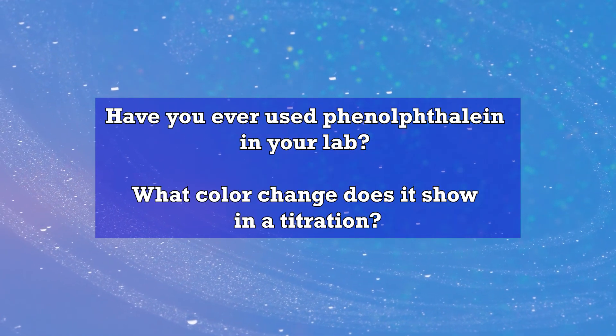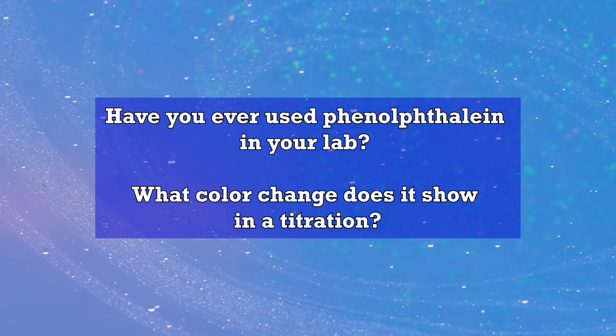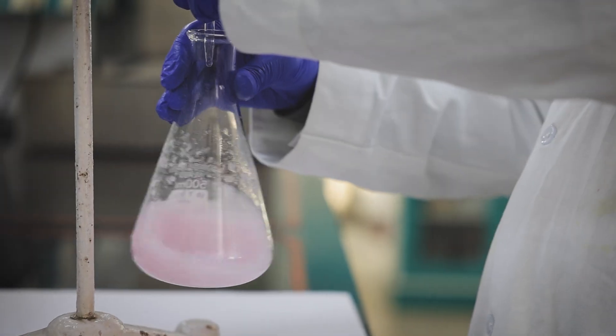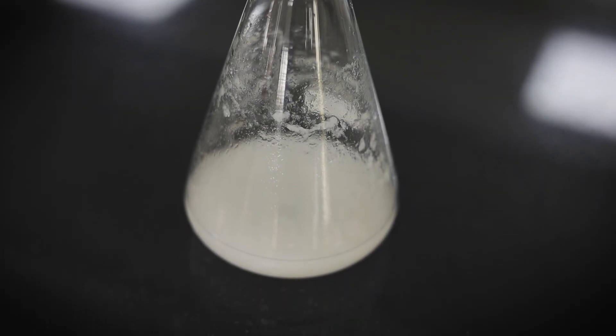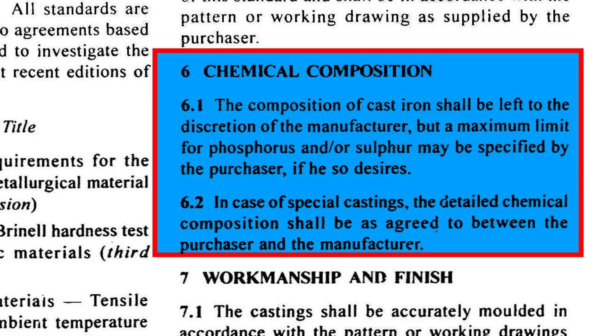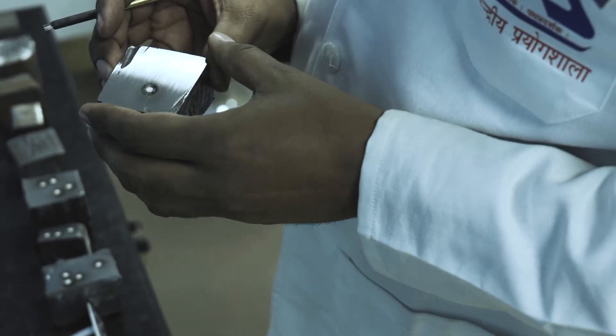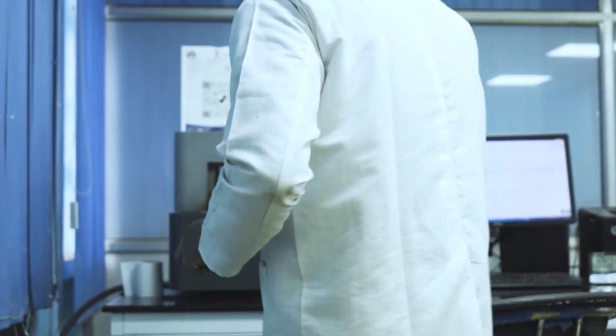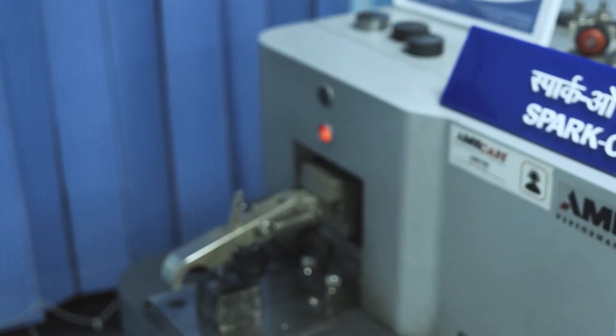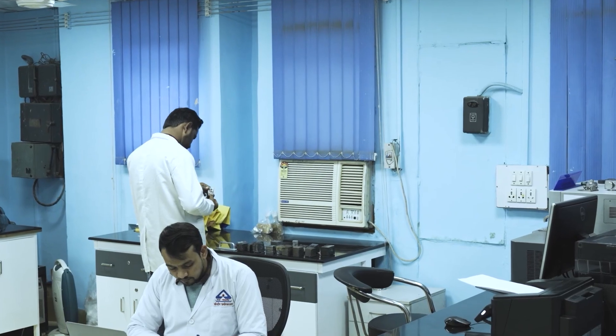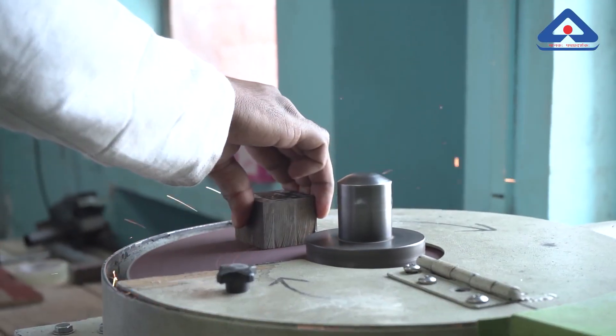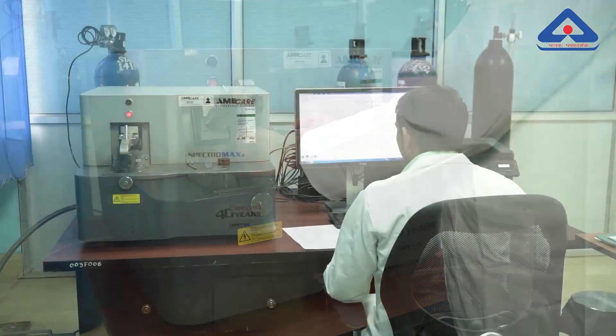We have seen that many reagents and chemicals are used in this test. Have you ever heard phenolphthalein being used in your school lab? What color change does it show in a titration? Phenophthalein shows a pink color in basic solutions, and the color disappears when the solution becomes acidic. Sulfur can be estimated with a CS analyzer, which determines sulfur content by combustion in an induction furnace and measuring the resulting gases through infrared absorption. For special castings, the chemical composition can also be determined using spark optical emission spectroscopy, which analyzes samples by creating a spark on the surface and measuring the emitted light, providing precise and rapid results ensuring the castings meet required specifications.